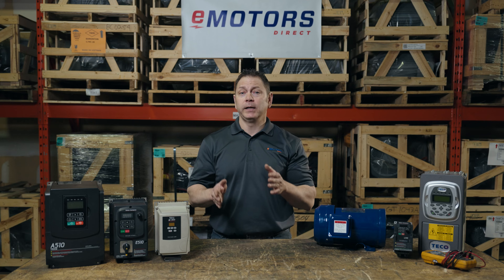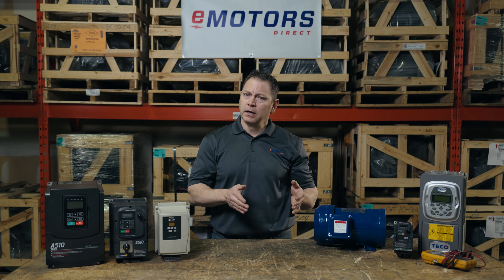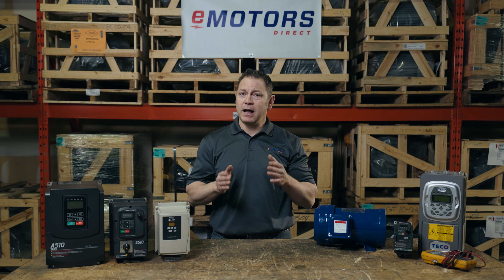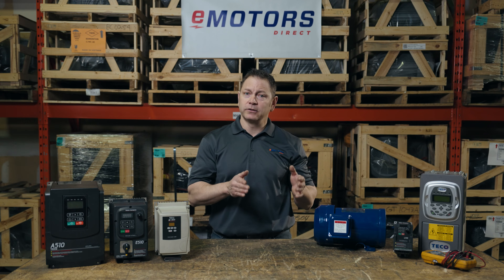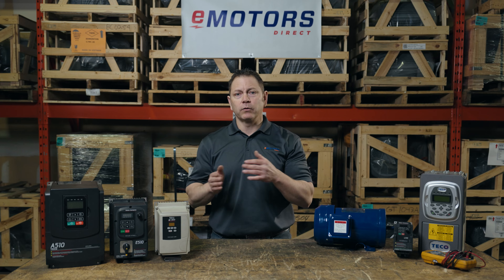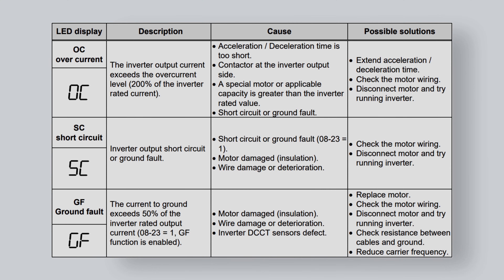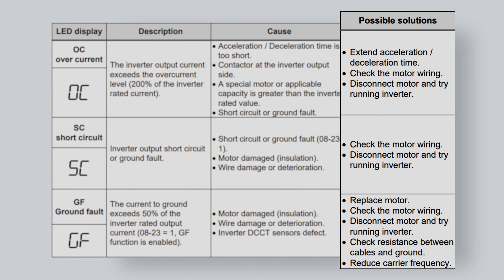Lastly, we'll look at nuisance failures — we'll be primarily looking at VFD fault codes. Check for active fault codes. If your drive has a display, it will show an error code. If your drive does not have a display, it will likely have a diagnostic LED that will blink or change color according to the error. Check your drive manual for a list of error codes or diagnostic LED states and follow the listed troubleshooting suggestions.